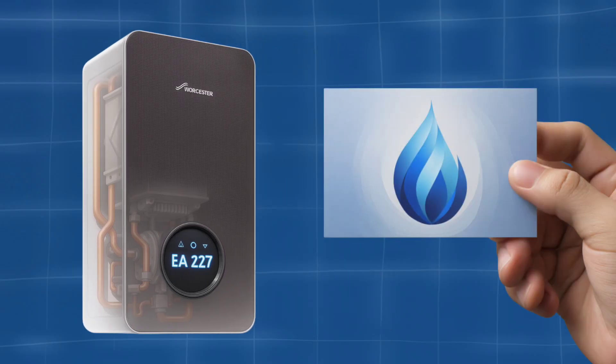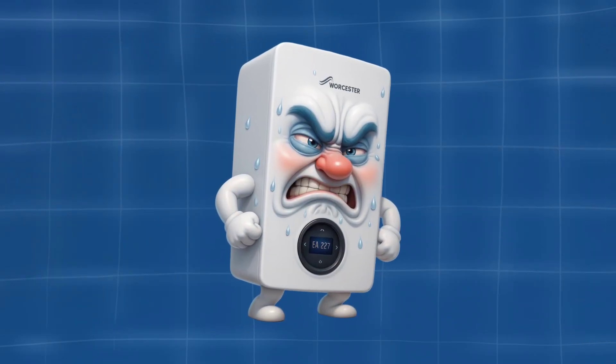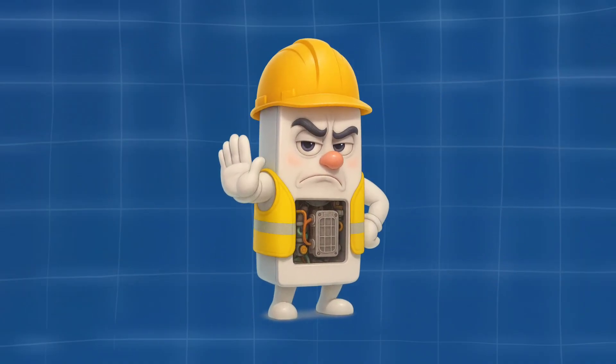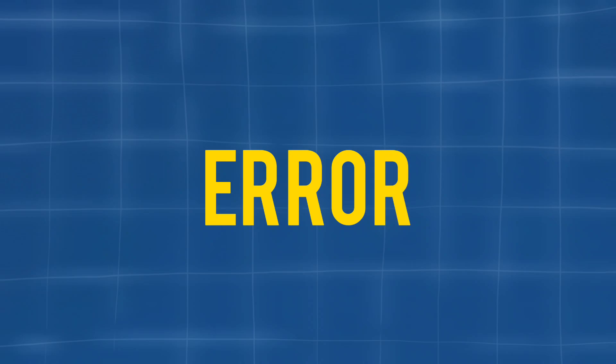EA-227 is a flame detection fault. The boiler's tried to light, but it hasn't sensed a flame, or it lost the flame during operation. So the system shuts down to stay safe. Now let's look at what can cause it.